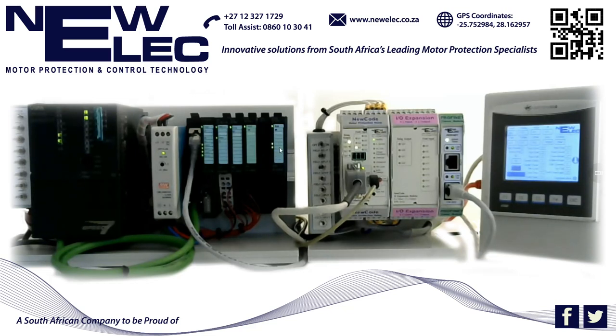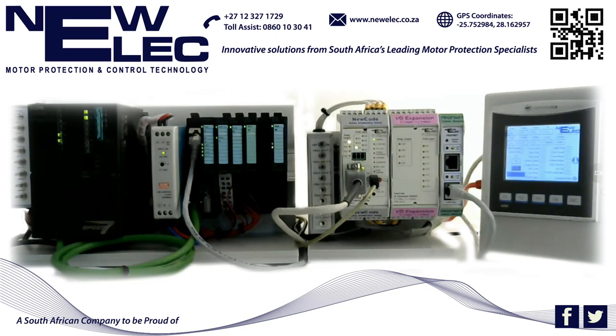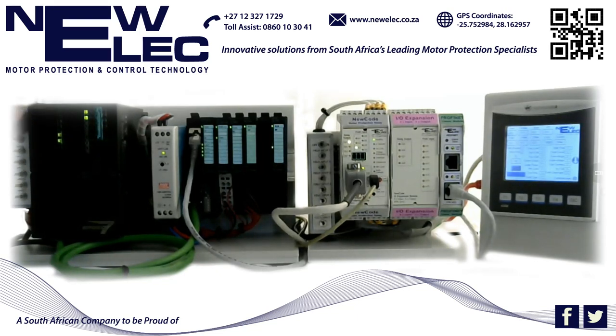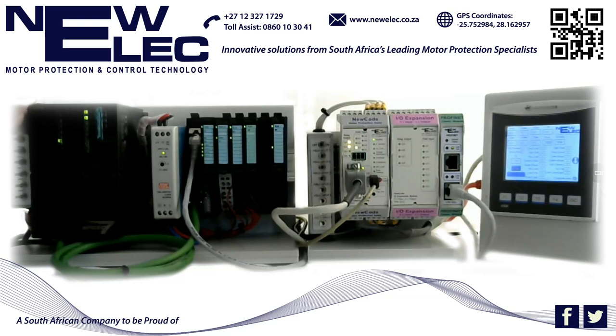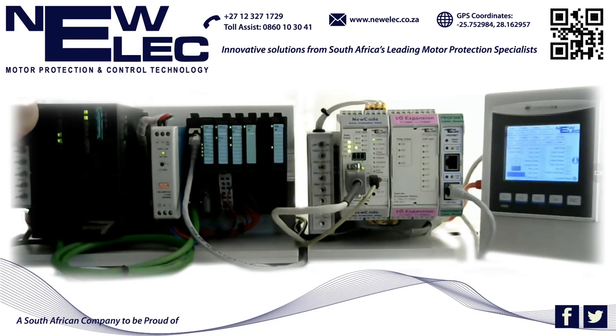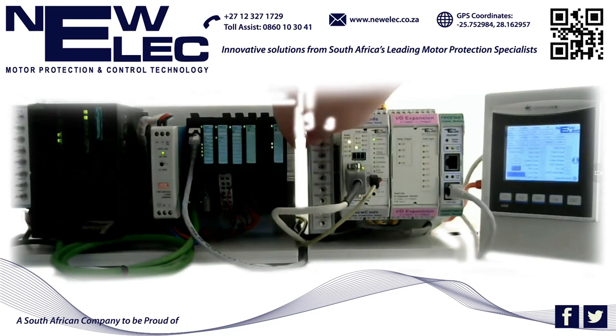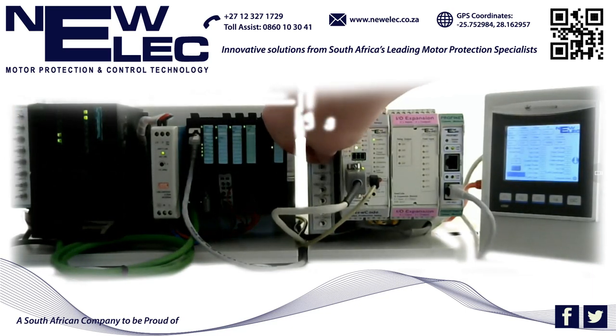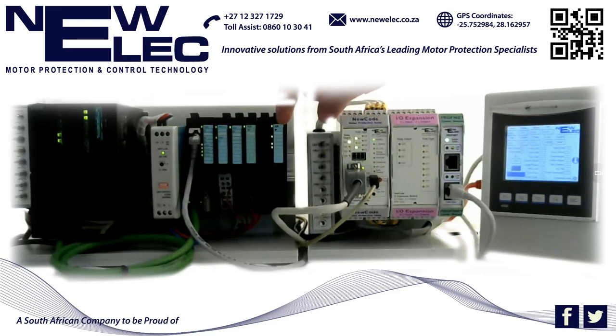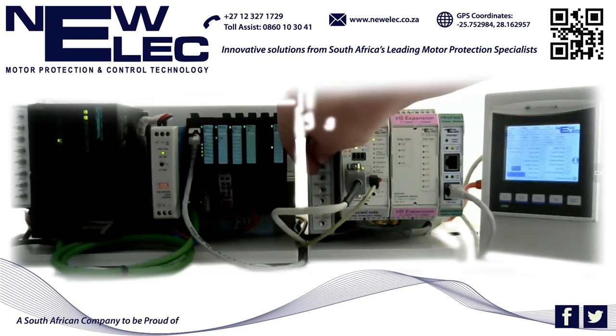Currently to show you how the cyclic data is interacting, if I'm switching field input 1 here on the PLC, you will see that relay 2 on the NewCode relay is switching on and off as I am switching this input. Same as with input 2, it's currently switching relay 3 on and off. If I go vice versa, if I switch the field input 1 on the NewCode relay, you will see that the input 1 LED comes on. If I switch input 2, the input 2 LED comes on.